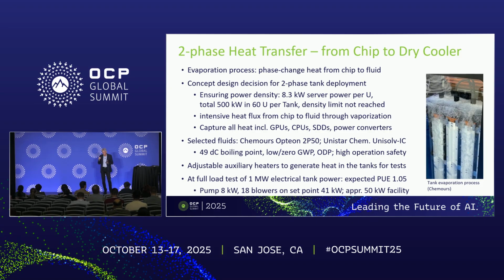We wanted to see how much reserve is in the fluid and how it works thermodynamically. For our test, we don't have computers to test here - we use adjustable heaters, switching them on and off to simulate the load, and we're expecting a very low PUE of 1.05.